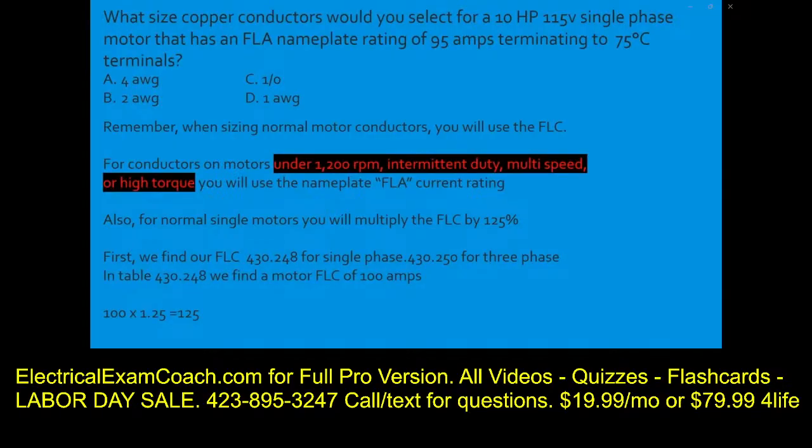Now we head to our primary ampacity table in the 75 degree C column. In the copper side, we're going to go down and select a wire that will cover our known amp draw, in this case, 125 amps. And we're going to select D.